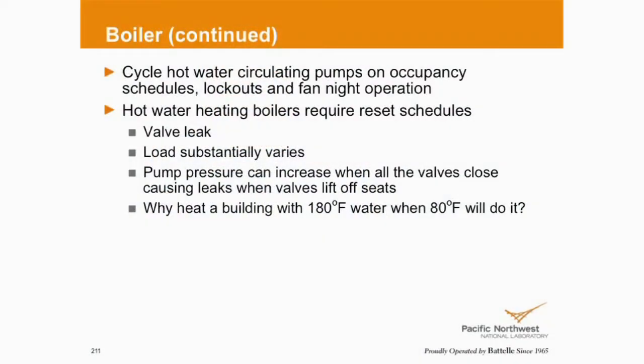Some of the reasons why we would want to have a reset schedule is, as I've said already, valve leaks. If I'm going to leak hot water, I'd rather leak 100, 120 degree hot water than 160 to 180 degree hot water. This is another one, third bullet down. Differential pressure in my hydronic loop can increase to the point that valves that say they're closed all of a sudden lift.